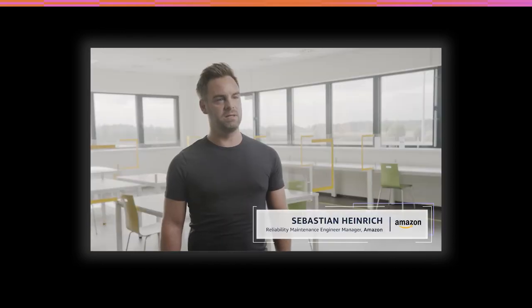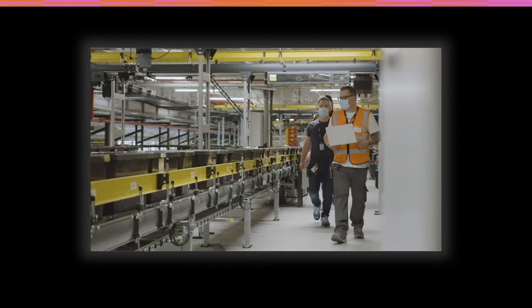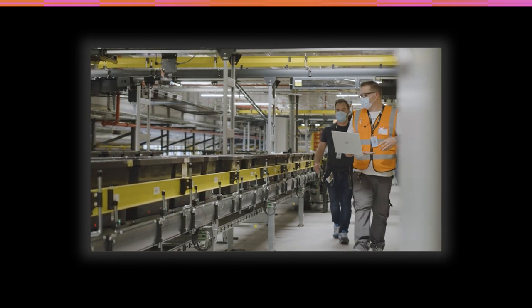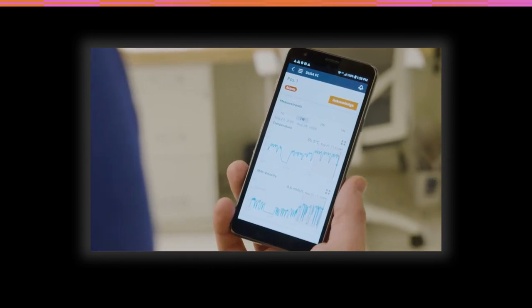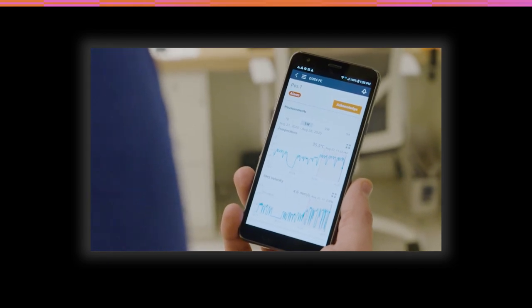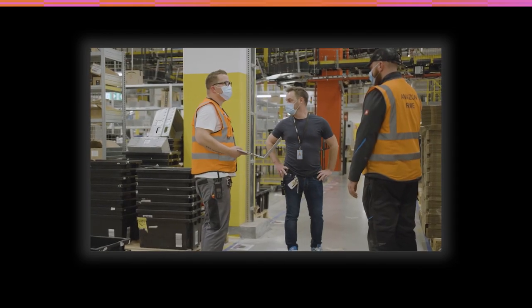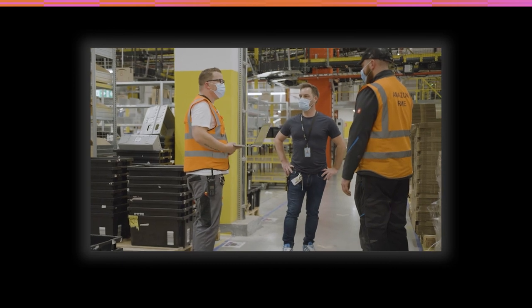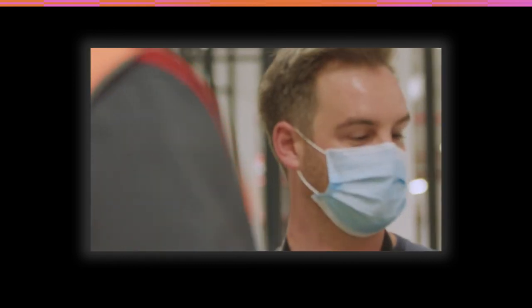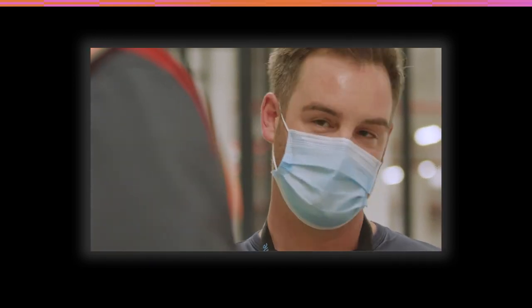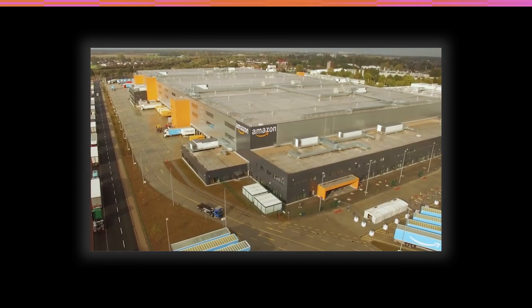We have an indicator and the sensor gives us the signal. We have a defective motor, so we saw the temperature was very high. The team made the decision to exchange the motor before we have an outage. And we can work together with operations to set up the maintenance window at the right time and make sure that we have no impact on the customer.